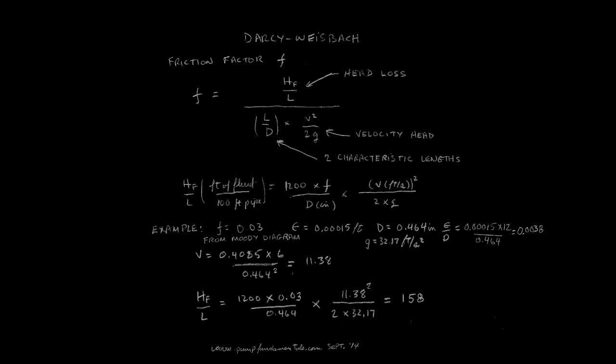L over d is a ratio of two important characteristics of the system. Let's put in 11.38 feet per second for v, 0.03 for f, and 0.464 for d. These values are the ones used in the previous pump and process video. The result is 158 feet per 100 feet of friction head loss.